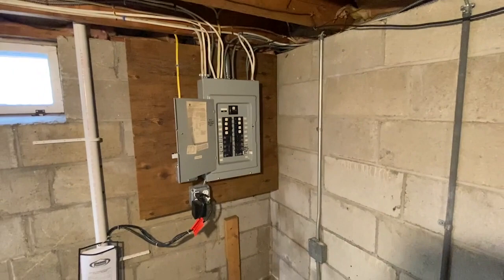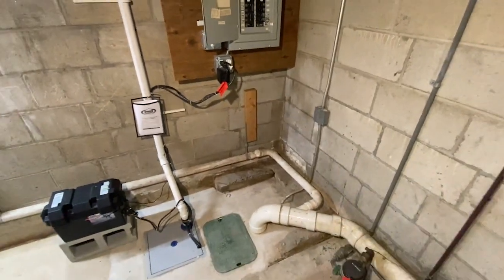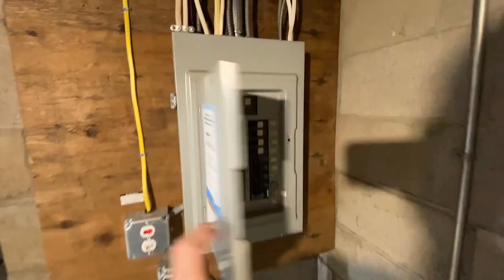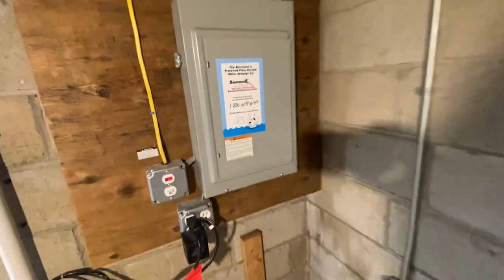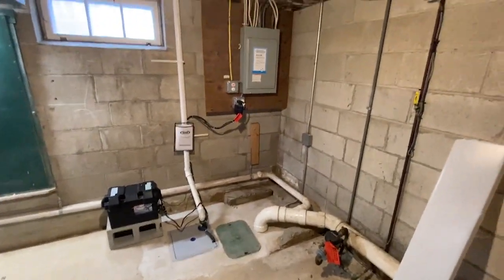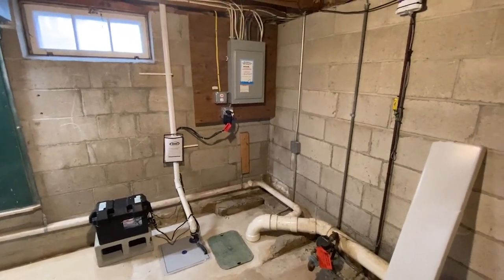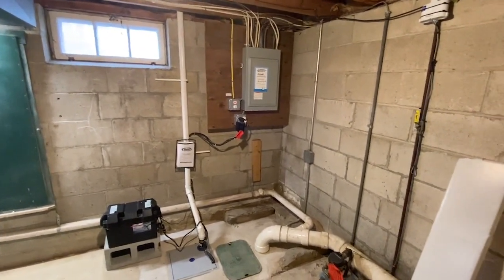Hello and welcome to Moving Violations. This is Russ LeBlanc, NEC Consultant for EC&M Magazine. It's going to be kind of difficult to stand and work safely and comfortably on this panel board. Looks like somebody added some drain pipes for some type of basement water drainage system. But in any case, all this white PVC piping is in our workspace in front of this panel board.